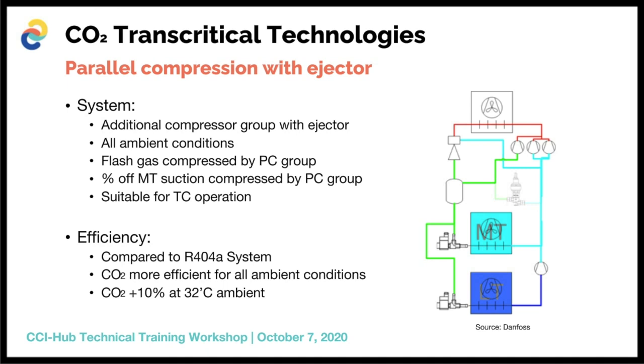As mentioned, these savings are depicted at ambient conditions of about 32 degrees Celsius. The energy efficiency increase is obviously higher when it's running at lower ambient conditions, like with any other system. Compared to its Freon counterparts, or 404A at this stage, the lower the ambient conditions, the more the energy efficiency gain would be. The showcasing here is specifically aimed at high ambient conditions, to show that technologies do exist that make these systems feasible and energy efficient, and not just environmentally friendly and sustainable solutions. There are a lot of additional technologies as well. The installation side of your CO2 system also leads to energy efficiency. This is literally just comparing the specific technologies that can be utilized.